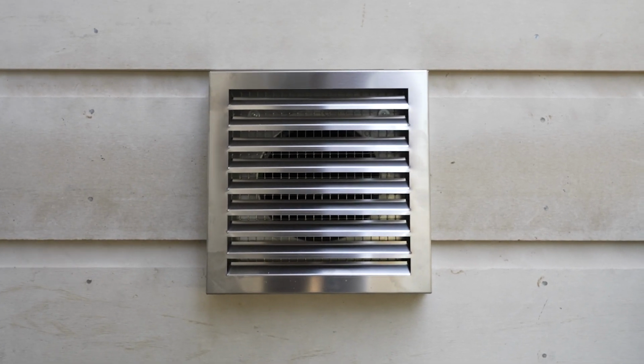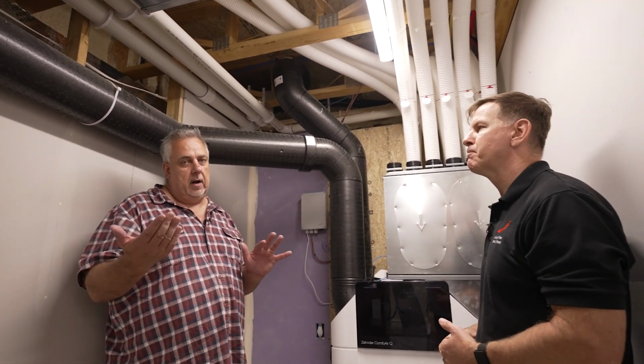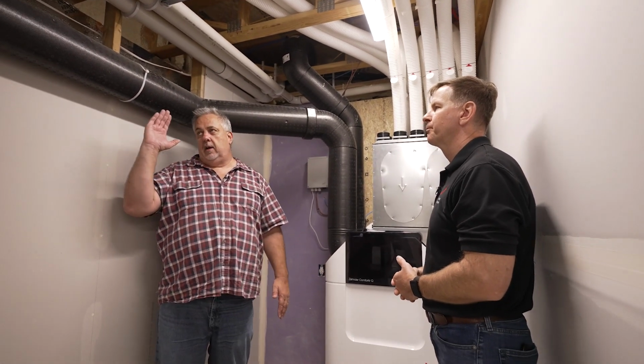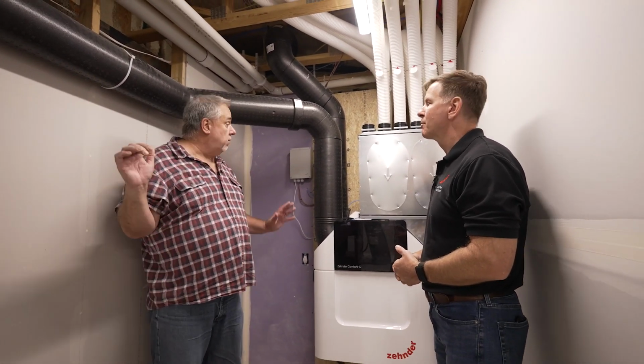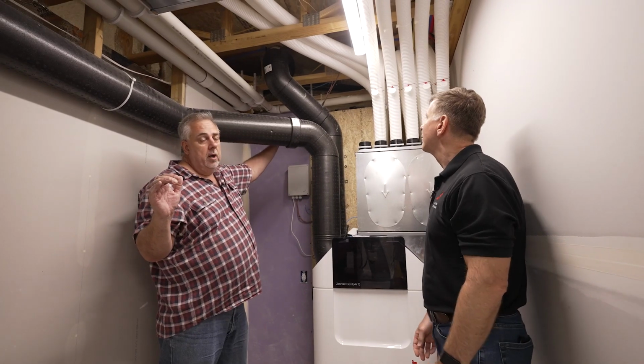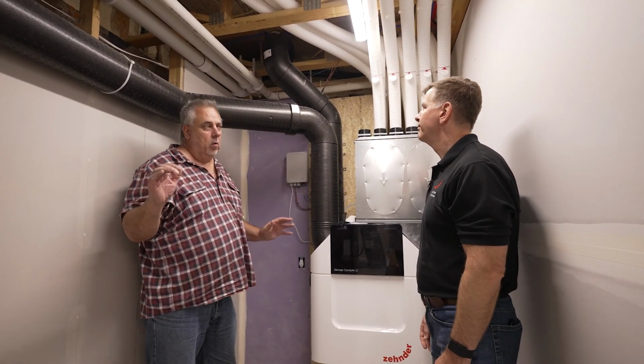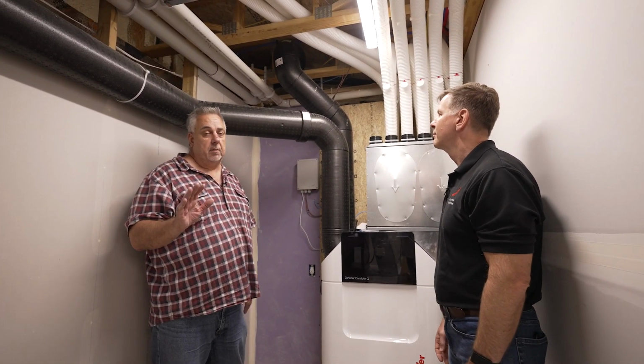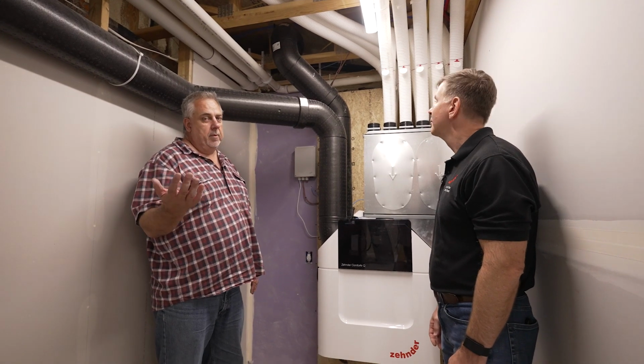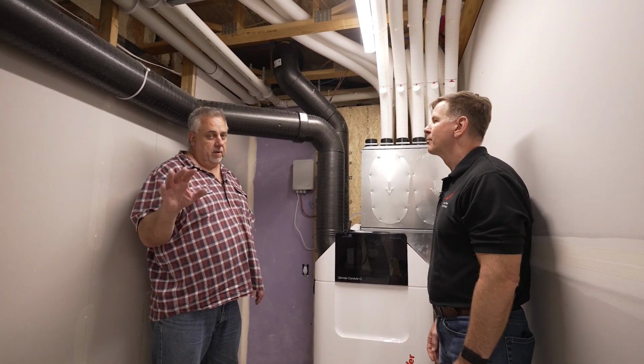Now, one thing to notice, we don't have to go down and see the outlets, but there's a minimum displacement, I believe, Chris, right? It's like 10 feet? Yeah, typically in codes it's 10 feet. It's 10 feet, yep. And I like to get it so that if I can get one on one plane of a wall and turn the corner and get it on a second plane of the wall, I think that's an even better system.